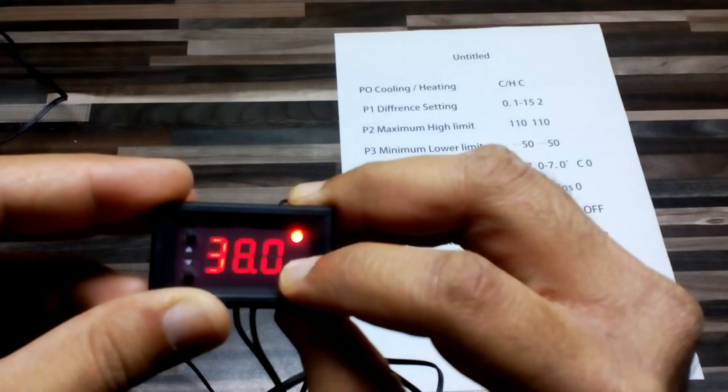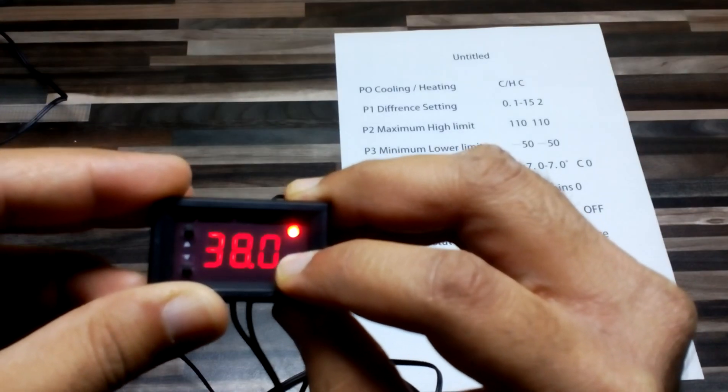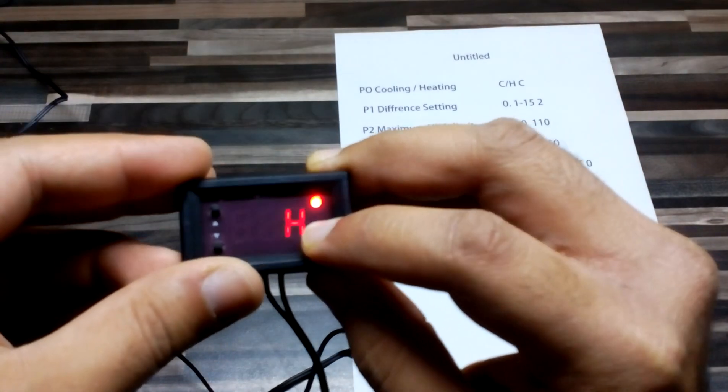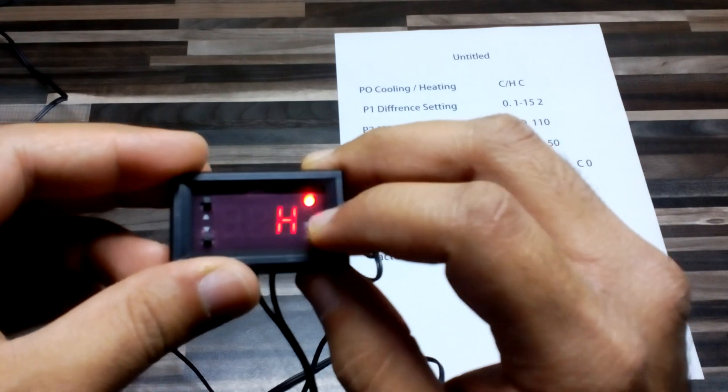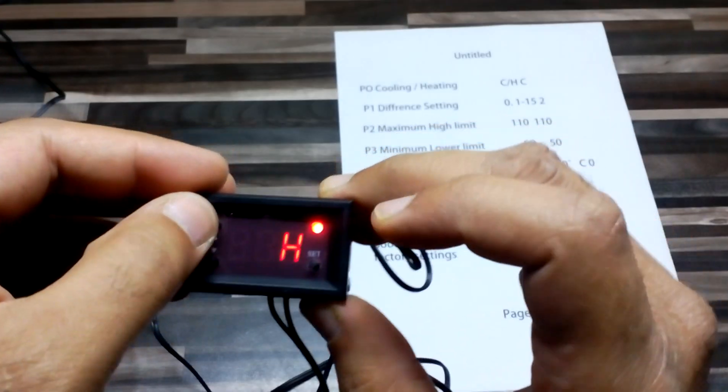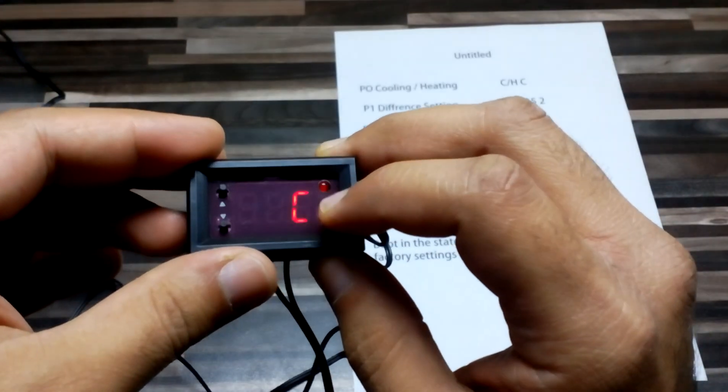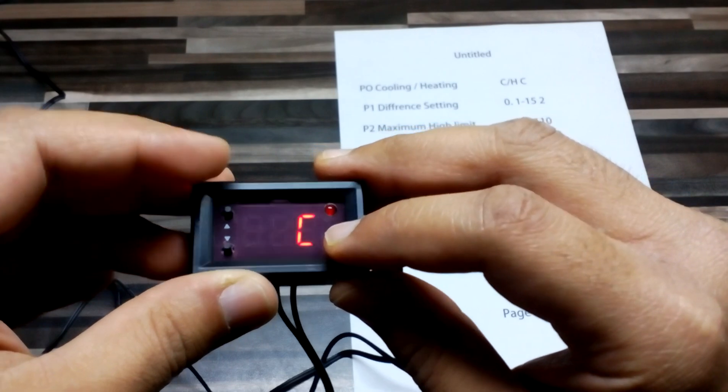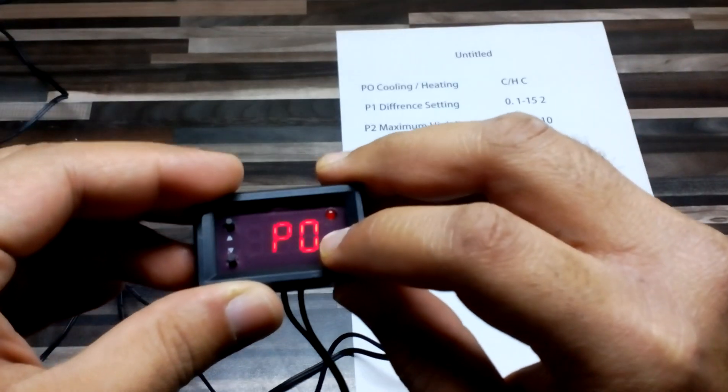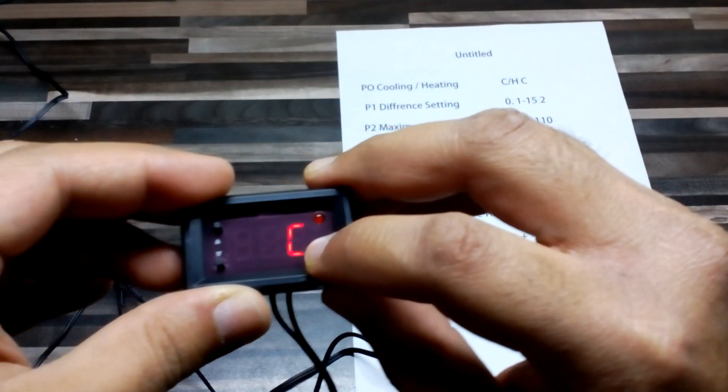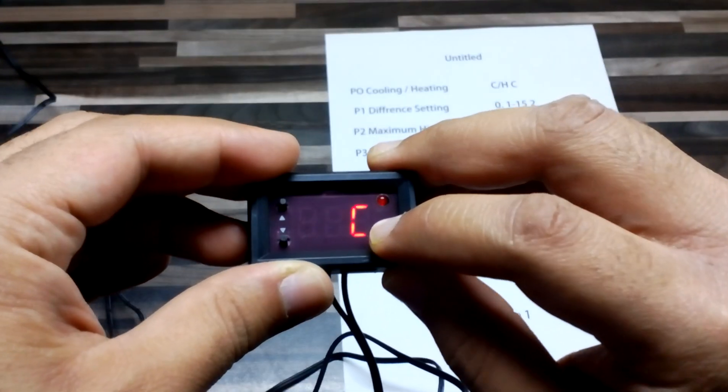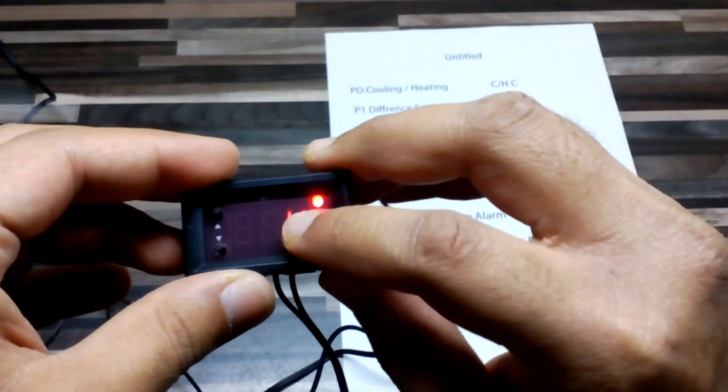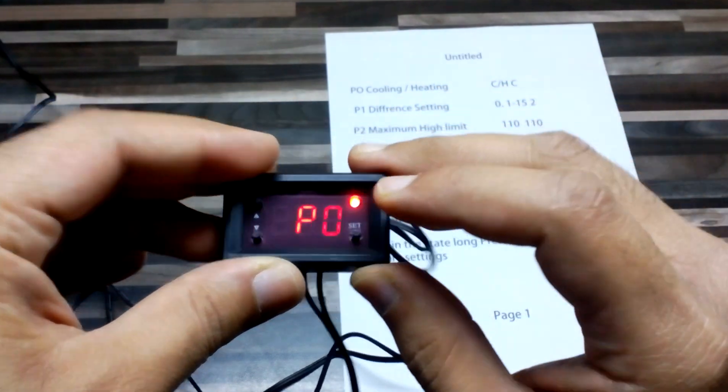For the internal setting, I'm going to press the set button until it reaches P0. On P0, we want it for heating, not cooling. If you want cooling for a fan or refrigeration, you can put the C button, but we want heating, so I'm going to put it on the heating button.